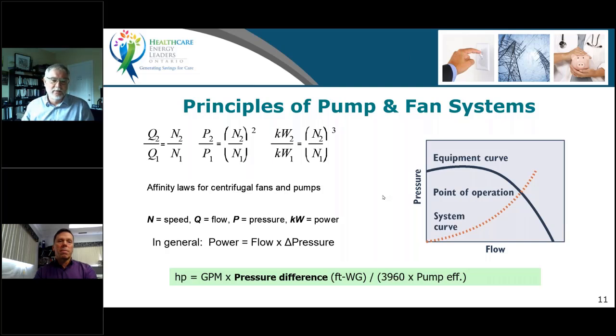Now, the relationship overall for the power required is a product of the pressure and the flow, or the differential pressure and the flow. So any operating point on this curve over here on the right-hand side, we can calculate the power based on the pressure and flow implied. And I'm going to come back to that one in a few minutes.